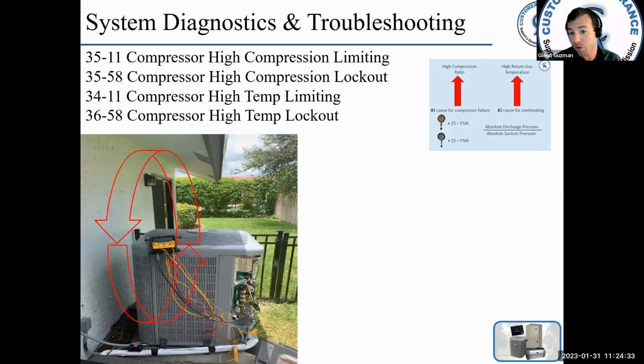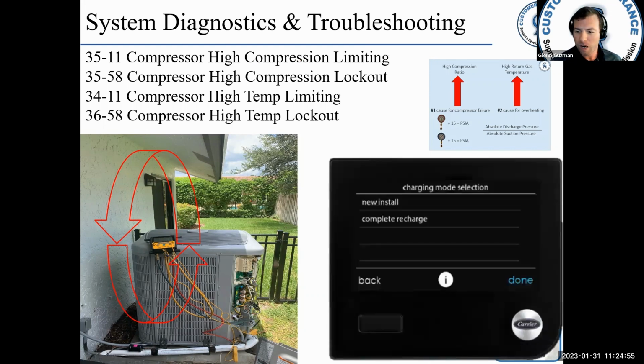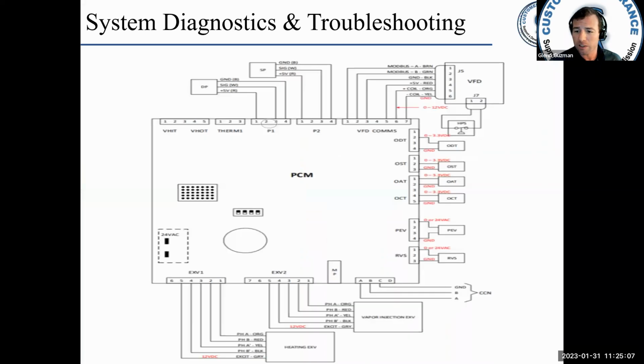What can cause a high compression ratio? Recirculating discharge air. If you look at this unit, the way it's installed, that air is hitting the eave of the house and coming right back down and just recirculating, artificially driving up the head pressure to a point where we get to this high temperature limiting, high compression limiting, and lockout. Okay. Maybe the unit's overcharged, and that's why you have a high compression limiting fault occurring. You may need to recharge the system.